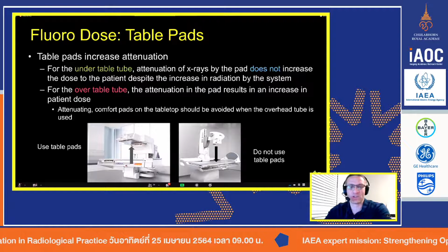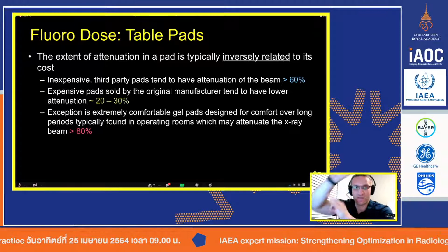Now, not all pads are created equally. There are some pads out there, and they tend to be the inexpensive, cheaper versions, things that you can buy from third-party vendors. They tend to be made of really attenuating material, lots of gel, lots of foam. And so these can actually attenuate the beam by 60%. I've seen them upwards of 60%. That means the machine has to put that much more radiation through your patient to create the same quality of image. So A, it can affect image quality, but B, depending on if it's an over-tube, that can really increase the dose to your patient quickly.